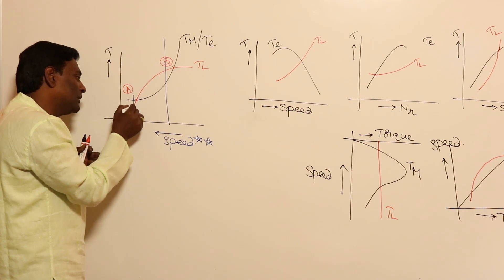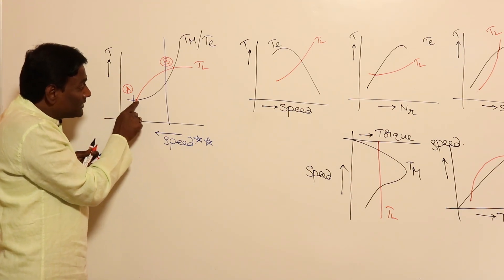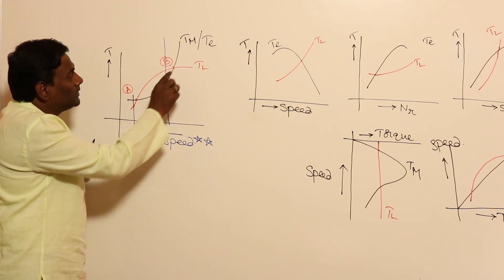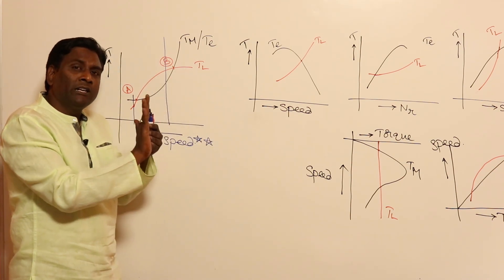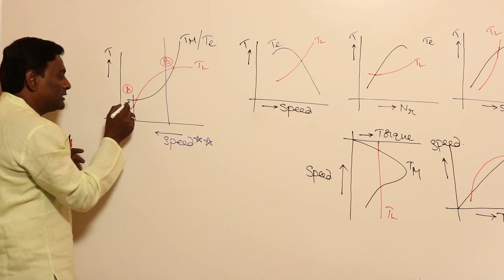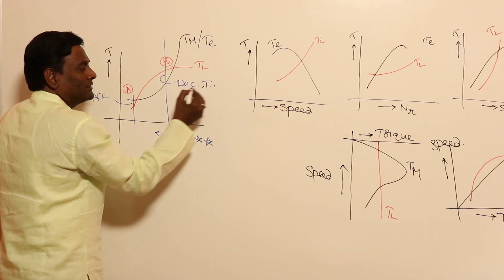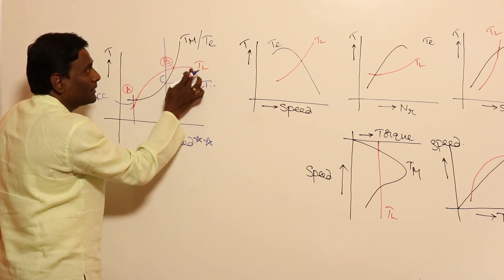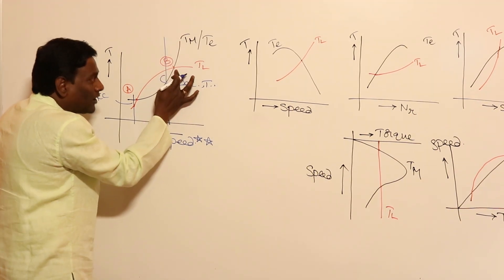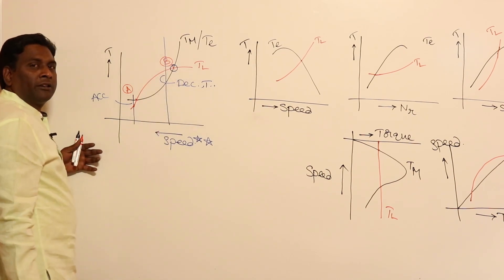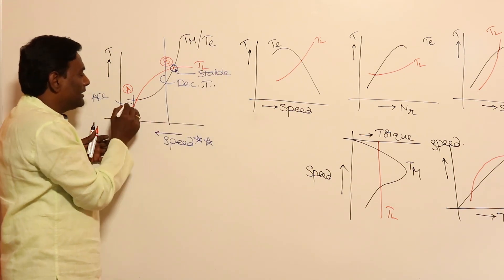Immediately after the junction point, in the direction of increasing speed: if motor torque developed is more and load torque requirement is less, it results in accelerating torque — that point is unstable. If load torque is more and motor torque is less, it results in decelerating torque — meaning the motor returns to that point, so it is a stable operating point.